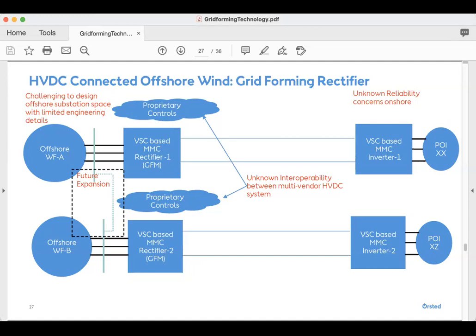Again, there were lots of engineering details missing. This is probably one of the requests that was not fully thought through, and there were lots of challenges. To the best of our knowledge, we don't know if vendors can guarantee interoperability between two different HVDC lines and converter stations. There's lots of proprietary control in VSC-based HVDC, especially if it's grid forming. And from an ISO perspective, it was unclear if the ISO had studied reliability concerns, especially when joining two different POIs via an AC interlink in the ocean.